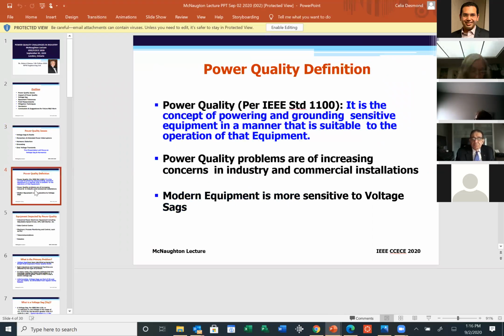Power quality. The way IEEE standard 1100 defines it, it is the concept of powering and grounding sensitive equipment in a manner that is suitable to the operation of that equipment. Let me put it in a much simpler way. Electrical equipment is designed to properly operate within certain voltage supply deviation tolerances, and this is typically plus or minus 10%, and over a certain duration.